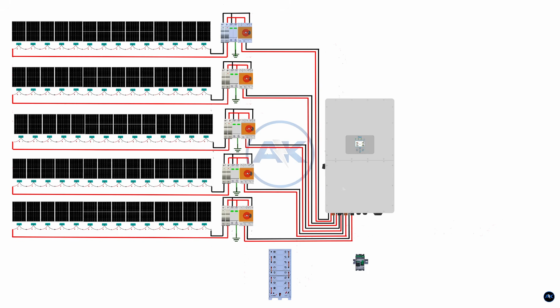The battery system includes built-in protection through the BMS, or Battery Management System. The BMS protects against overvoltage, undervoltage, overcurrent, short circuit, and temperature faults. Even with this protection, safe wiring is still essential. We always connect the battery system in this order: grounding first, power cable second, and communication cable last.